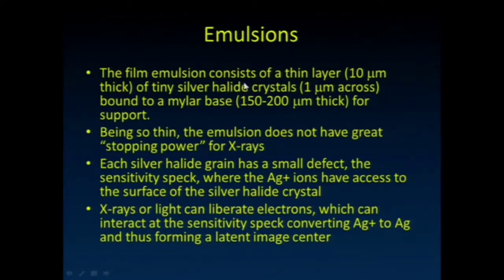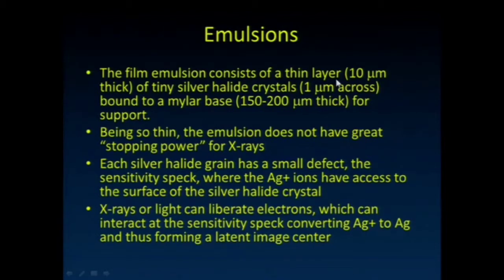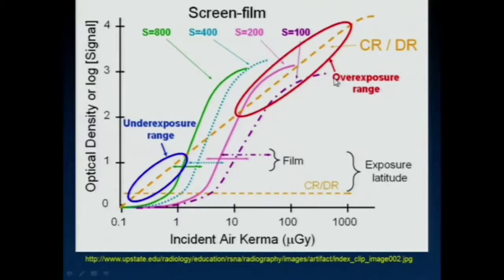Film had this silver halide emulsion on a plastic mylar backing, and visible light — film does a really nice job stopping visible light — but that thin silver halide layer really doesn't do a very good job stopping X-ray energies. So instead, we had to put something in front of that which did a better job stopping the X-rays and converting them to visible light that was better matched to the absorption characteristics of the film.